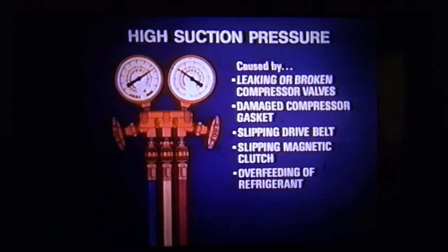High suction pressure may indicate leaking or broken compressor valves, a damaged compressor gasket, a slipping drive belt or magnetic clutch, or overfeeding of refrigerant by the expansion valve caused by a valve stuck open or an improperly insulated feeler bulb. Check the louver temperature against the performance chart. Temperature readings will vary with room temperature and relative humidity.